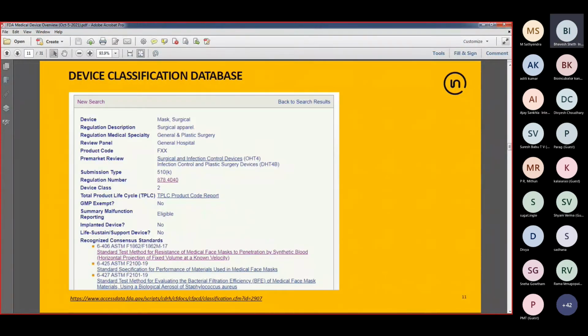So I've selected an example here for a surgical mask. When I go to the product classification database and I type in surgical mask, I end up with this classification. Now, I want to spend a little more time on this page, explaining what information you can find when you look up the classification. The first piece of information you're looking at is the device common name, which is surgical mask. Then there is a regulatory description, which is surgical apparel. So the surgical mask belongs to a category called surgical apparel. And if you look at the regulation number, 878.4040, that's 21 CFR 878.4040. That regulation number is tied to this regulation description, surgical apparel.